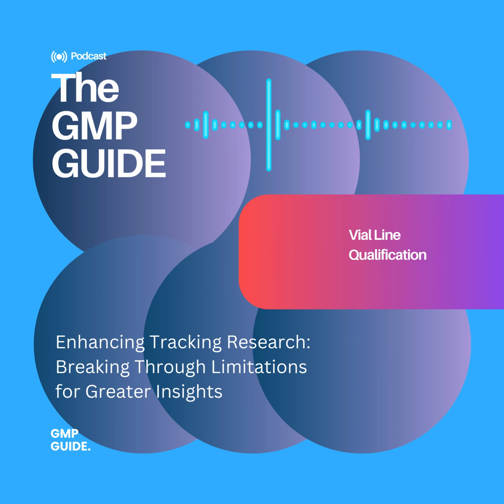Tag 3.2: operational qualification, OQ. Okay, once that meticulous installation qualification is complete and everything is physically in place and connected correctly, we then move on to operational qualification, or OQ. This is the phase where we determine that the equipment's performance is entirely consistent with the user requirement specifications, and that it reliably operates within the manufacturer's specified ranges. It's where we identify and meticulously inspect features that directly impact the final product quality. Does it actually work as intended? And remember, this only happens after a successful IQ. You can't skip ahead. That's right.